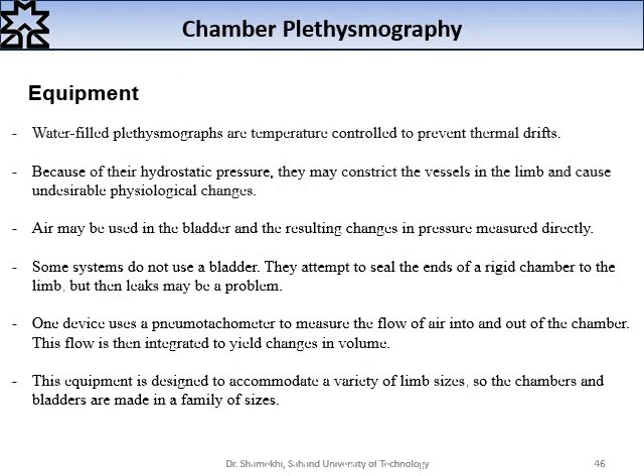From the device perspective, the following points should be noted. Water-filled plethysmographs are temperature controlled to prevent thermal drifts. Because of their hydrostatic pressure, they may constrict the vessels in the limb and cause undesirable physiological changes. Air may be used in the bladder and the resulting change in pressure measured directly. Some systems do not use a bladder. They attempt to seal the ends of the rigid chamber to the limb, but then a leak may be a problem, maybe a big problem.